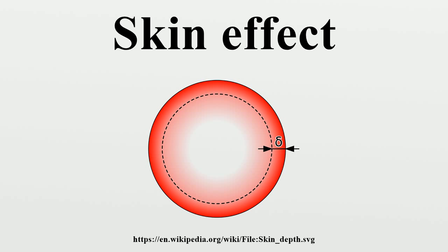In Engineering Electromagnetics, Hayt points out that in a power station a bus bar for alternating current at 60 Hz with a radius larger than 1/3 of an inch is a waste of copper, and in practice, bus bars for heavy AC current are rarely more than half an inch thick except for mechanical reasons. Skin effect reduction of the self-inductance of a conductor.